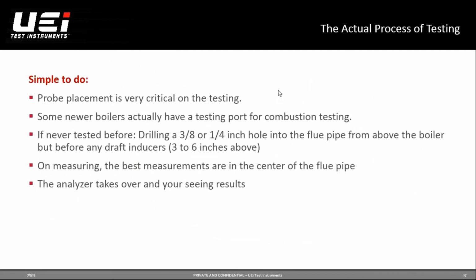There is a nice little probe, and depending on if you're doing boilers or furnaces, there's a lot of new boilers who actually have a testing port already built into them. But if you're not that lucky, all you have to do is drill about a quarter inch hole into the flue pipe. You're going to do that above the boiler or furnace, but before any of the draft inducers, and that's kind of where that sweet spot is.